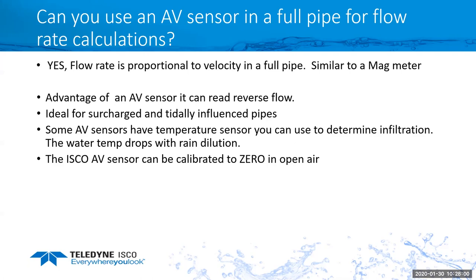Another option for calibrating AV sensors, like the ISCO sensors, they are temperature calibrated. The advantage of that is you can take that sensor, calibrate it to zero level in open air, and then install it in your channel. I've found, especially on higher velocity applications, this ends up being more accurate than trying to put a ruler in the water and measuring, because of how the water rises up on the ruler, it makes it difficult to get an accurate level reading.